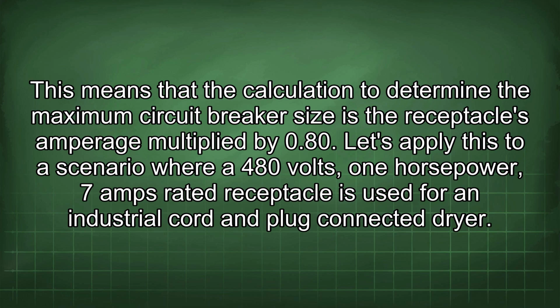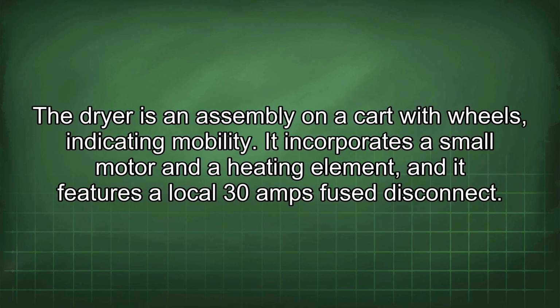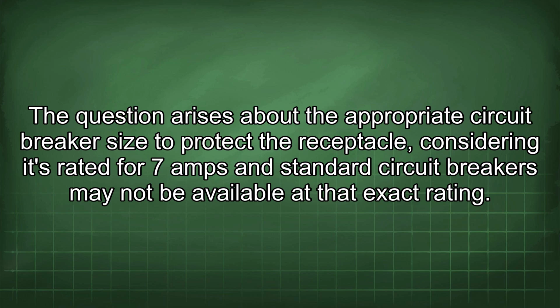Let's apply this to a scenario where a 480 volts, 1 horsepower, 7 amps rated receptacle is used for an industrial cord and plug connected dryer. The dryer is an assembly on a cart with wheels indicating mobility. It incorporates a small motor and a heating element, and it features a local 30 amps fuse disconnect. The question arises about the appropriate circuit breaker size to protect the receptacle, considering it's rated for 7 amps and standard circuit breakers may not be available at the exact rating.